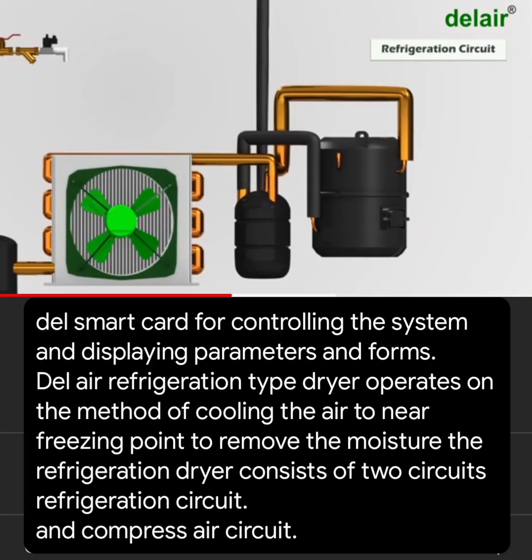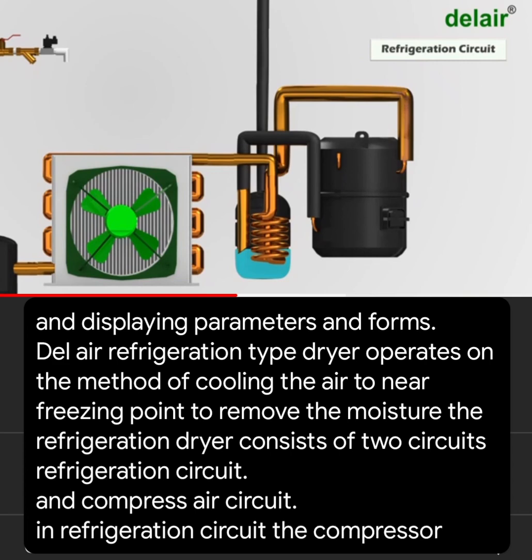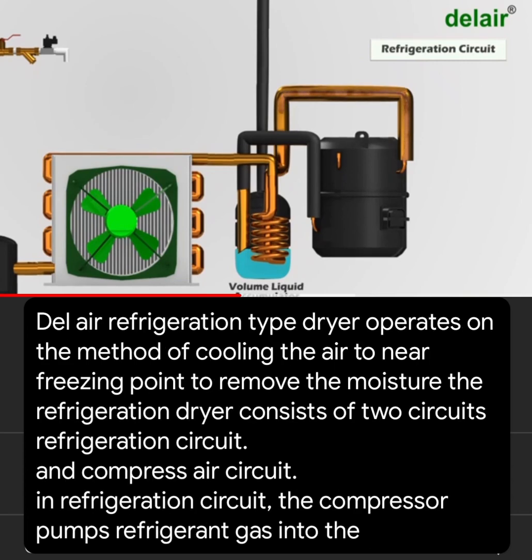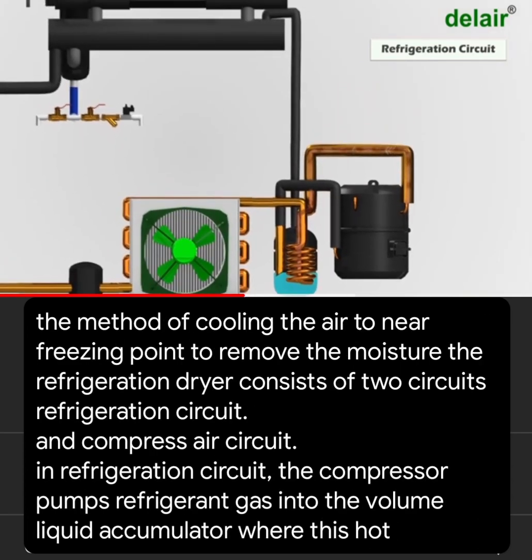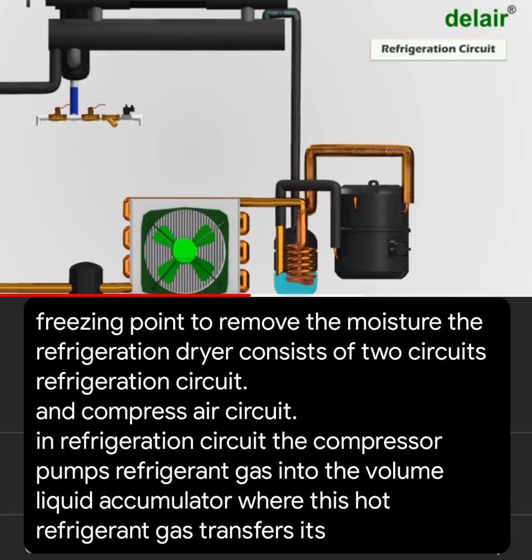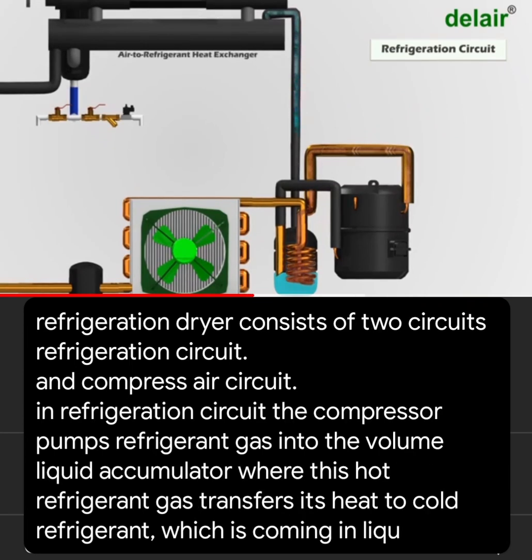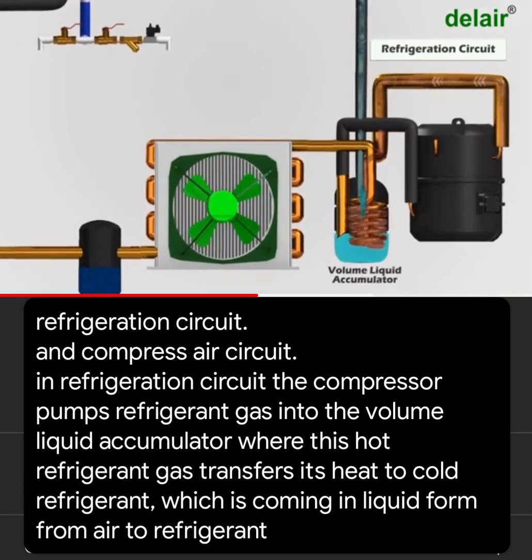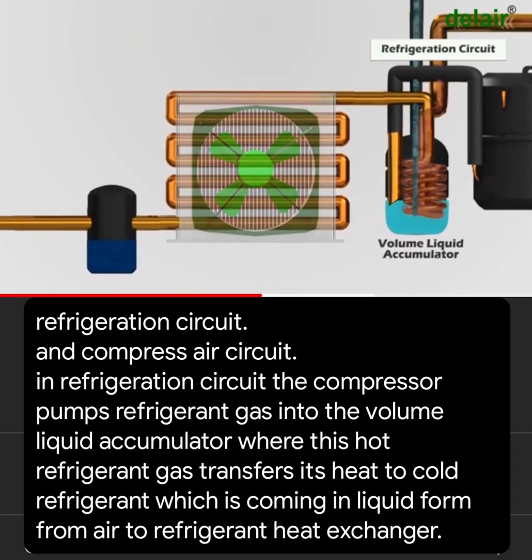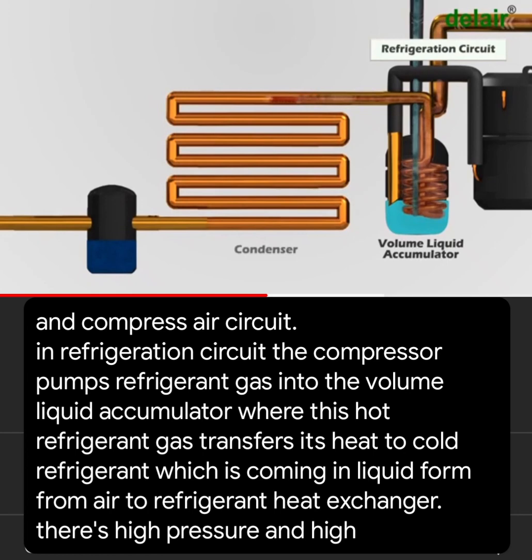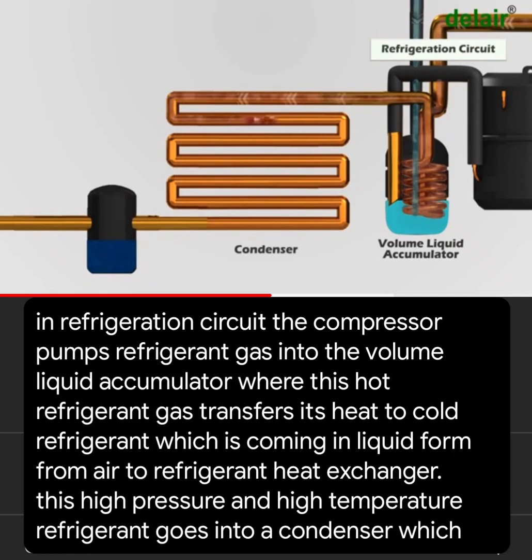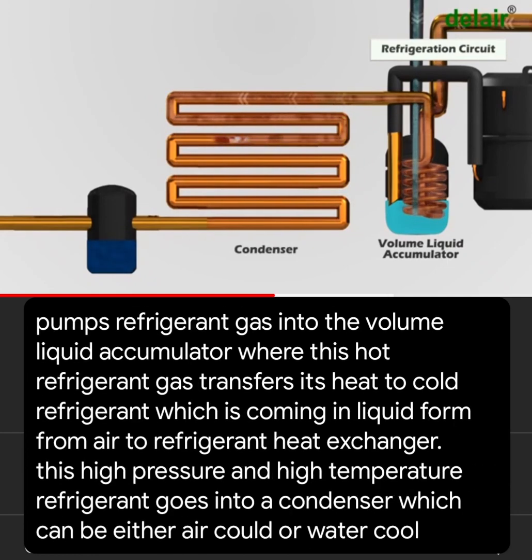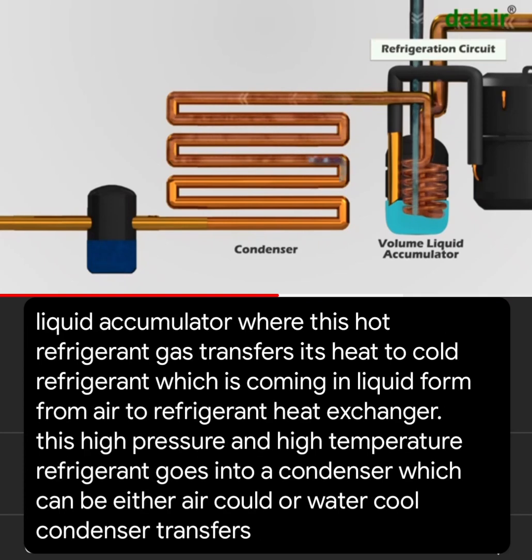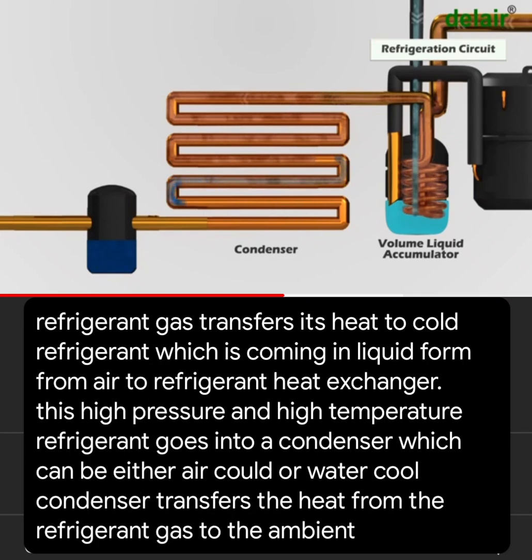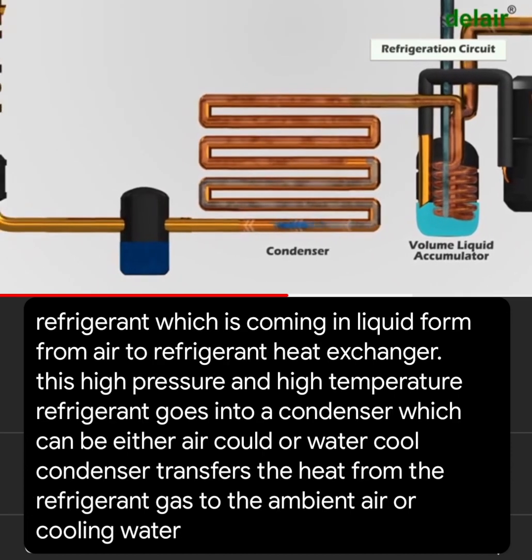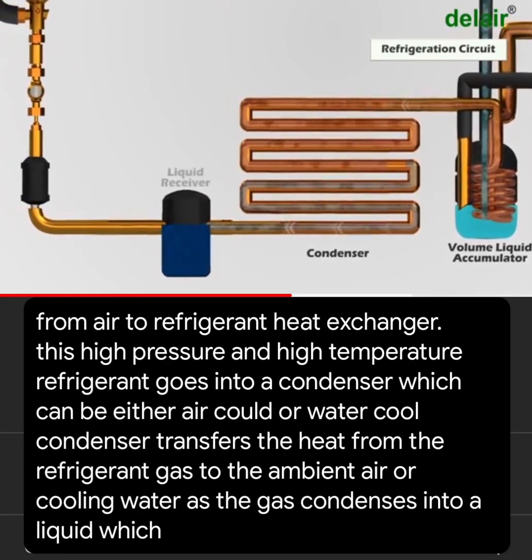In the refrigeration circuit, the compressor pumps refrigerant gas into the volume liquid accumulator, where this hot refrigerant gas transfers its heat to cold refrigerant, which is coming in liquid form from the air-to-refrigerant heat exchanger. This high pressure and high temperature refrigerant goes into a condenser, which can be either air-cooled or water-cooled. The condenser transfers the heat from the refrigerant gas to the ambient air or cooling water as the gas condenses into a liquid, which is collected into a liquid receiver.